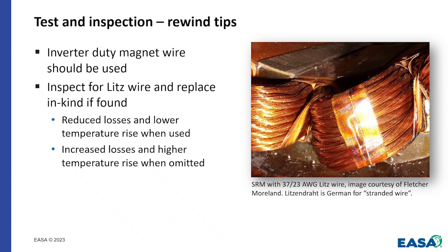When we're sometimes up into a couple of hundred hertz, that can be a severe condition. So what you'll see sometimes is use of what's called Litz wire, which just means stranded, but intentionally stranded. So it's not just getting 15 wires in hand. These wires have a pattern throughout the bundle that they're manufactured with.